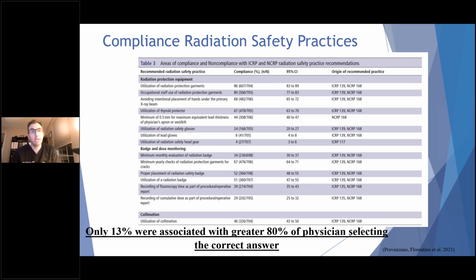We heard a little bit about badge and dose monitoring. You should have a minimum evaluation of your radiation badge monthly. You should check your lead for cracks on a yearly basis. Where should you store your badge? Where should you place your badge? Are you recording fluoroscopy times? Are you recording the cumulative dose as part of your operative procedure? And are you collimating, which we heard just about before? And what you can see is that the compliance rate, which is in the second column, was very, very poor.